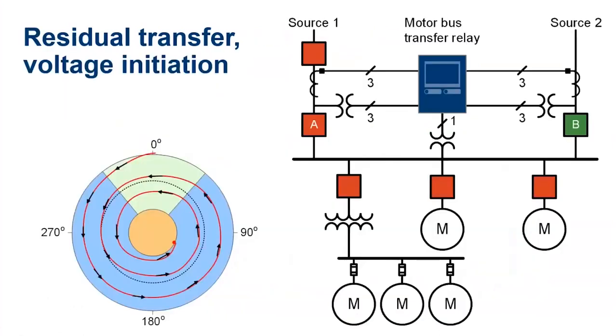Okay, so the last one is the residual transfer. And in this case, there was a too severe fault outside the system that brought all the voltages down too much before initiating the transfers, or you know that the motors cannot support. I mean, the inertia is too small and the voltage will decay too fast. So you would just wait until the voltage falls below a user-defined threshold.